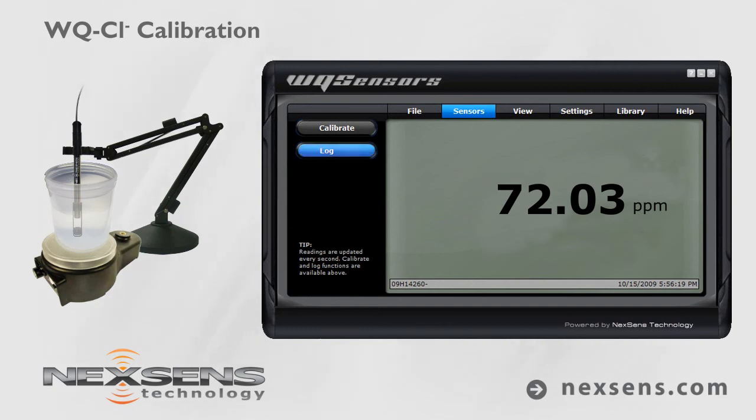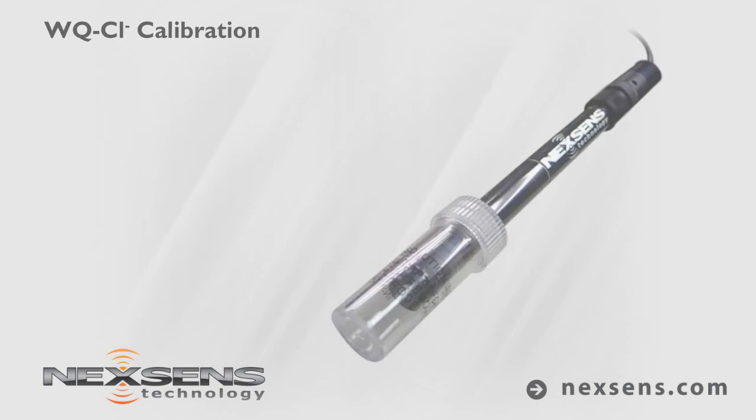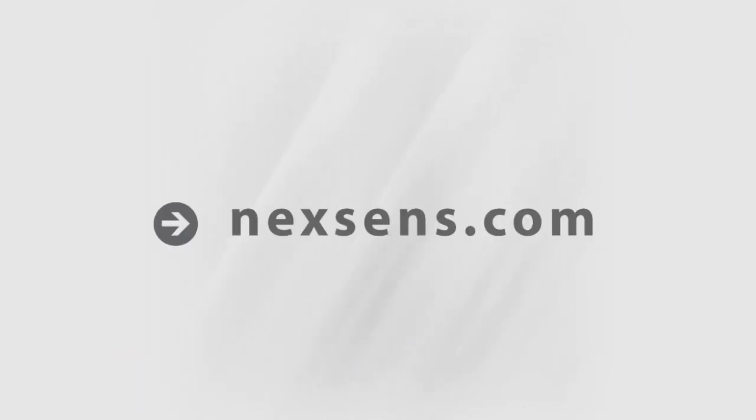Press the log button to store the readings with a date and time stamp. Quality data collection requires frequent calibration — for best results, calibrate before each use. When not in use, the WQ Chloride sensor should be stored in the bottle in which it was shipped. NexSens WQ sensors: the latest in smart sensor technology.